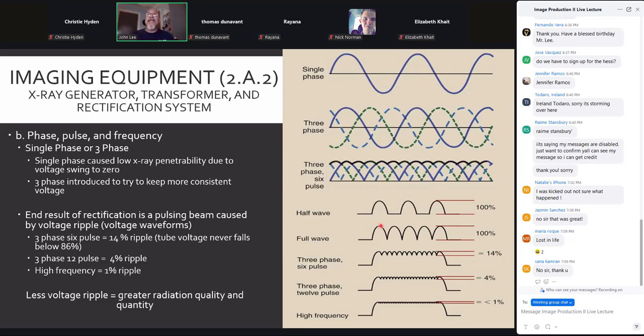So we're only at peak for a very, very small fraction of that cycle. The rest of the time, we're either building up to peak or going back down to zero. This is why we have such a heterogeneous beam when we produce X-rays. This is what is known as voltage ripple. All right. It goes from 0 to 100%, then back down to 0, and it's 100% ripple. That means if we set 100 kV, there's a very, very small percentage of X-rays that will be produced at 100 kV. The rest of them are going to be well below that, approaching 0.